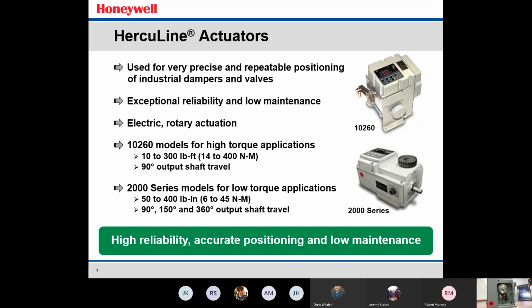These do have electric rotating actuation. So in some cases, we're supplying a 4 to 20 milliamp control signal to this actuator. Sometimes it's 0 to 5, 1 to 5, 0 to 10 volts from the control loop. In other cases, we're providing just a simple on-off discrete input to the actuator that allows it to increase or decrease the rotation on the valve depending on where the process needs to control at.